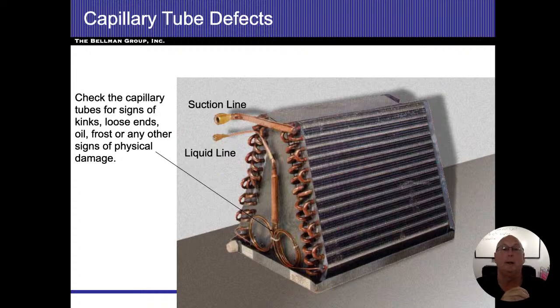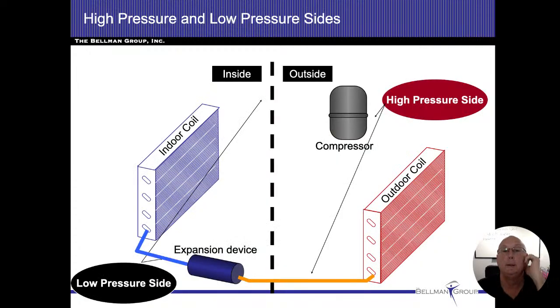Here's an actual A coil that comes in there. So you can see the skinny line, we call that the refrigerant line, and then that goes into those capillary tubes again. So the spinning of the capillary tubes that's on there, that's what's going to hold everything back. And you could see the fins. I like this picture a lot because we can actually see the coils and how they're going back and forth on there. We can see the fins, how they're tight and keep the air coming through as well. And then when it leaves through the thicker line up there, that's called the suction line. So it comes in as a liquid and leaves as a gas as we absorb all the heat that's inside the house and put it into the refrigerant. So now we're under low pressure. We're a liquid.